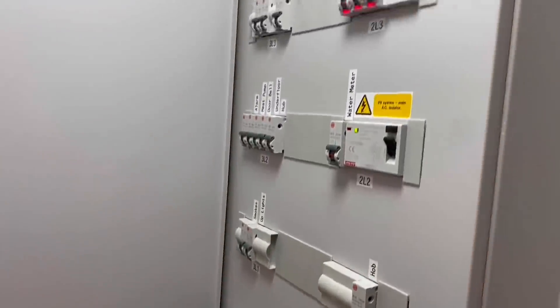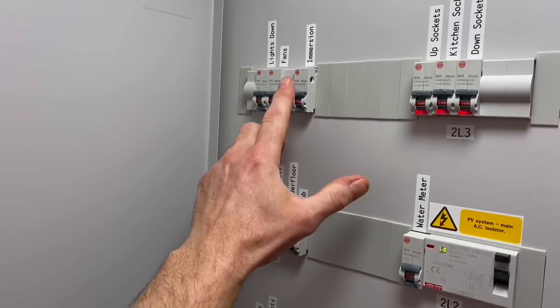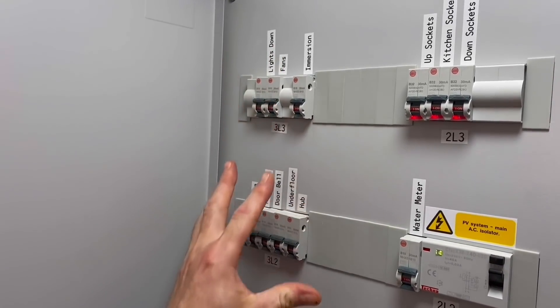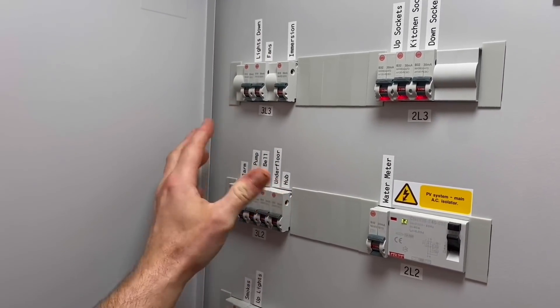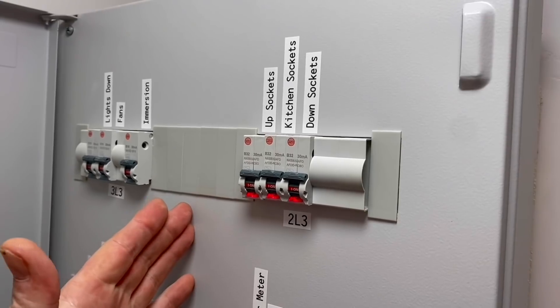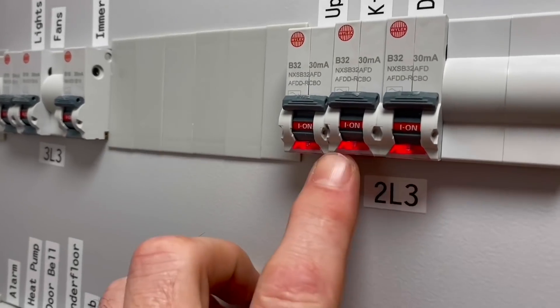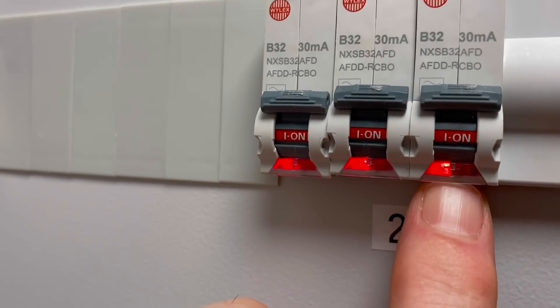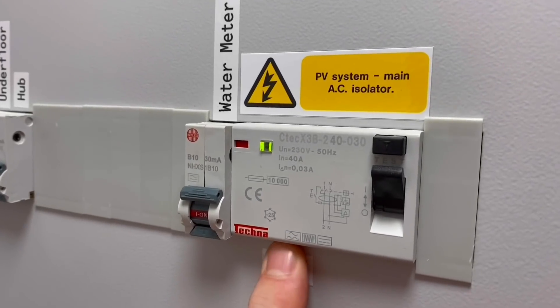These devices feed up to the top board, with the panel split into two sides. The left-hand side is what they call regulated - we know the load, so we know the wattage of the immersion and the lights installed downstairs. The other side is unregulated - we don't know the value of load, as anything could be plugged into the socket outlets. You'll also notice the little red LED underneath these breakers - those are the Wylex AFDDs. There's also an RCD for the solar PV, and the symbol makes this a B-type RCD.